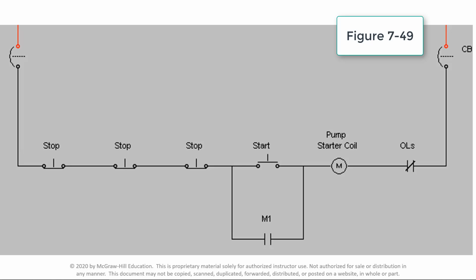This video demonstrates the operation of the NOR logic function. NOR logic is a combination of OR logic and NOT logic in which two or more normally closed contacts are connected in series to control the load. This simulated application is that of the NOR logic function used with 3-wire control to energize a motor starter.